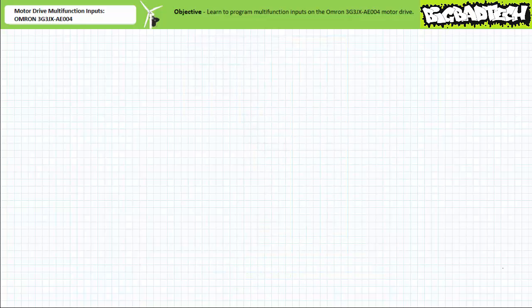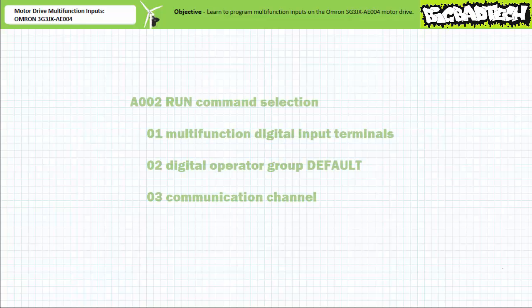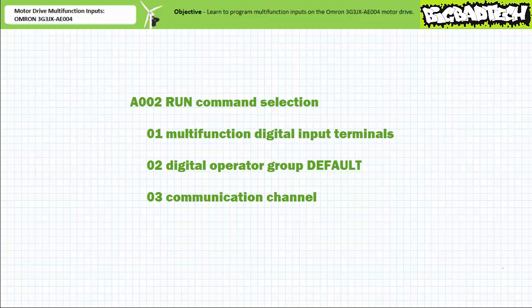The run command on the OMRON 3G3JX AE004 motor drive has a similar setting: extended function parameter A002, run command selection. 01 is the multi-function digital input terminals — this is the setting we'll make use of today. 02, the default setting, is the run and stop/reset button in the digital operator group. 03 is over a communication channel.